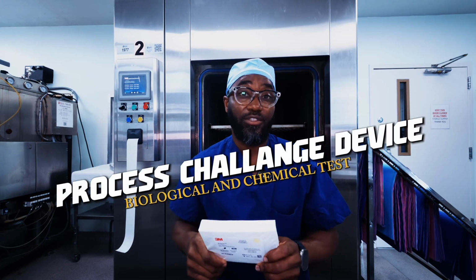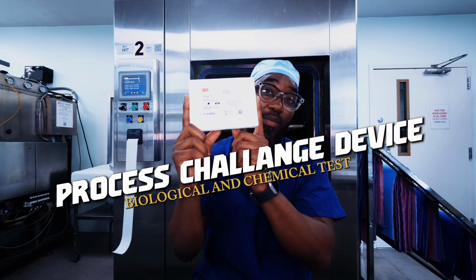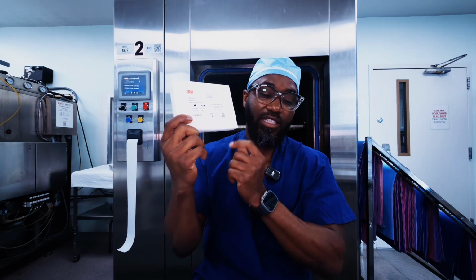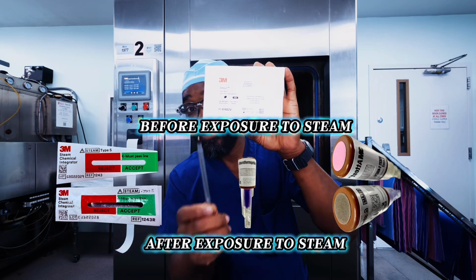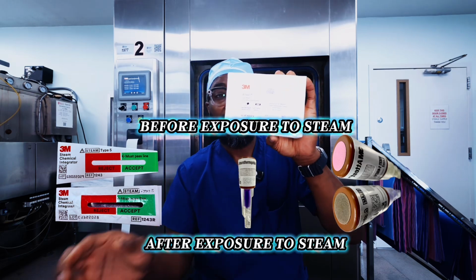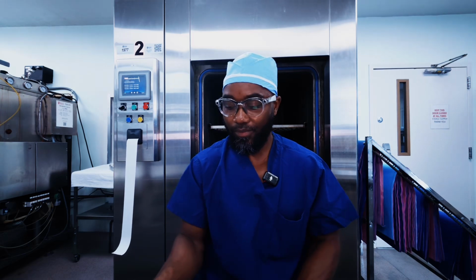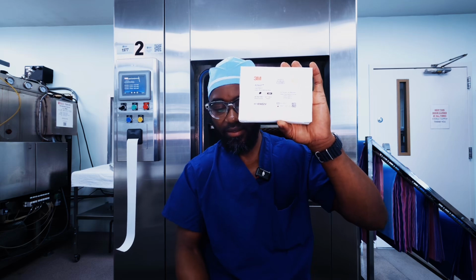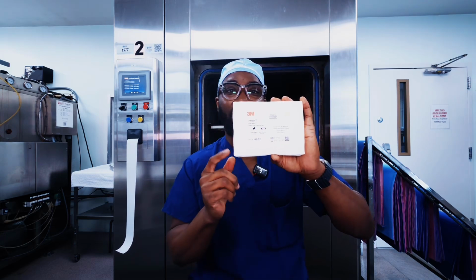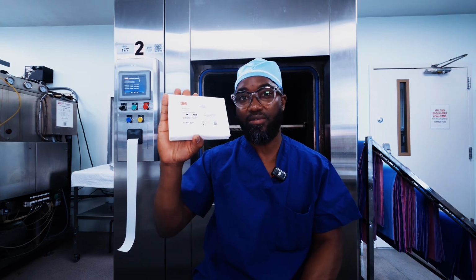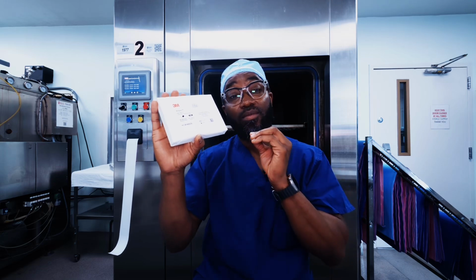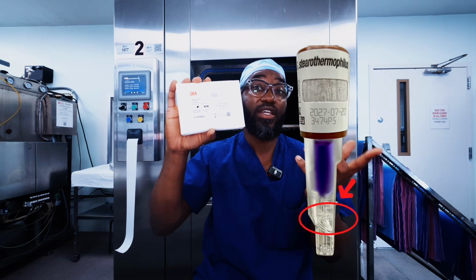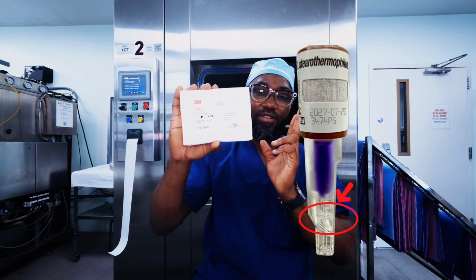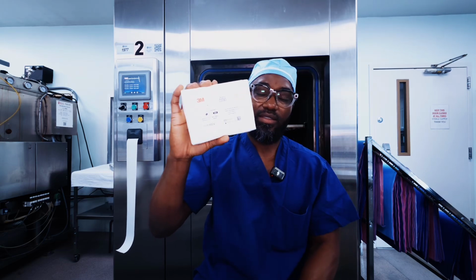Our process challenge device of choice is this biological test pack, which is also manufactured by 3M. Within this test pack, you have a type 5 chemical integrated indicator, and then you also have a biological indicator, which is filled with a spore called Geobacillus stearothermophilus. Why do we use this process challenge device? This is to measure the efficacy of steam sterilization within the autoclave. We are using the hardest to kill harmless microbial life form, which is a heat-loving bacteria. The rationale is that if this microorganism can die within the process of sterilization, it means that every other microbial life form on your instrument has died.